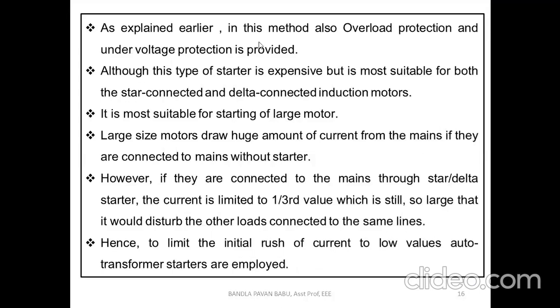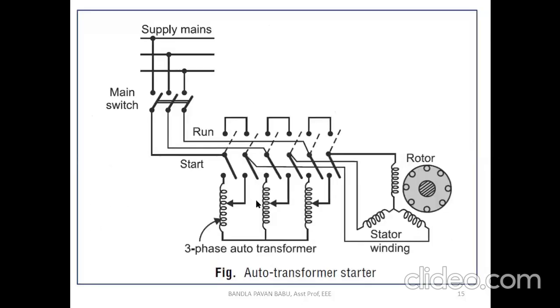As explained earlier, in this method also we use overload protection and under voltage protection, which is by default for all the methods. Next, although this type of starter is expensive, it is most suitable for both star connected and delta connected induction motors. It is most suitable for starting large motors, as I said before. Using an auto transformer is one of the best choices for high rating machines. Large motors draw a huge amount of current from the mains if they are connected without a starter. For high rated machines the short circuit current will obviously be very high, and we need to limit that. If you want to limit that, we can use this method. By using an auto transformer we regulate the current, and soon after reaching the rated speed, we can tap it to the full line voltage.